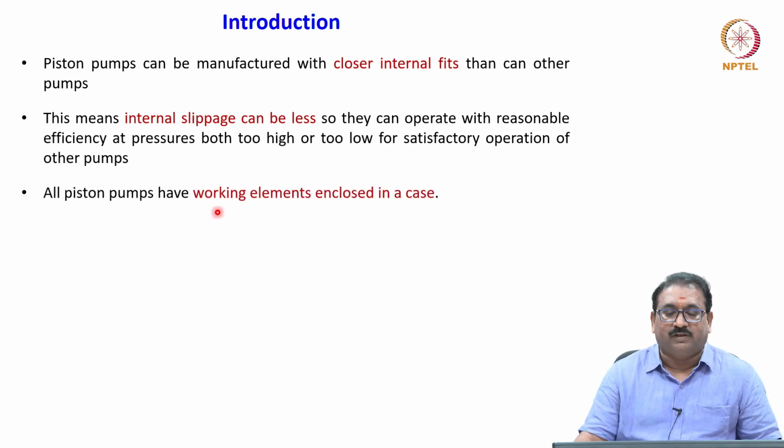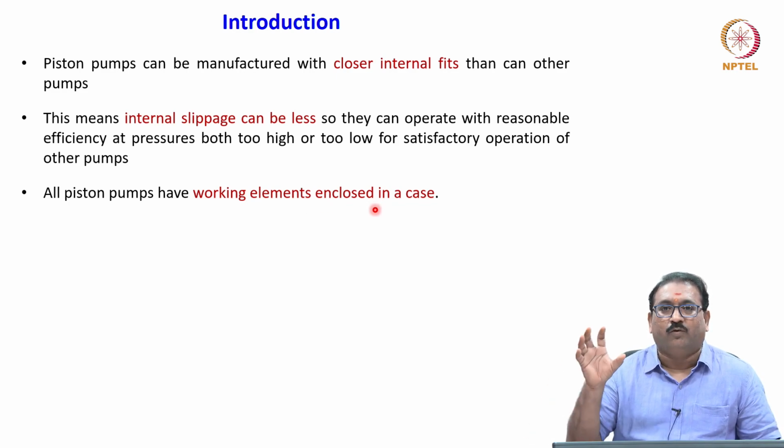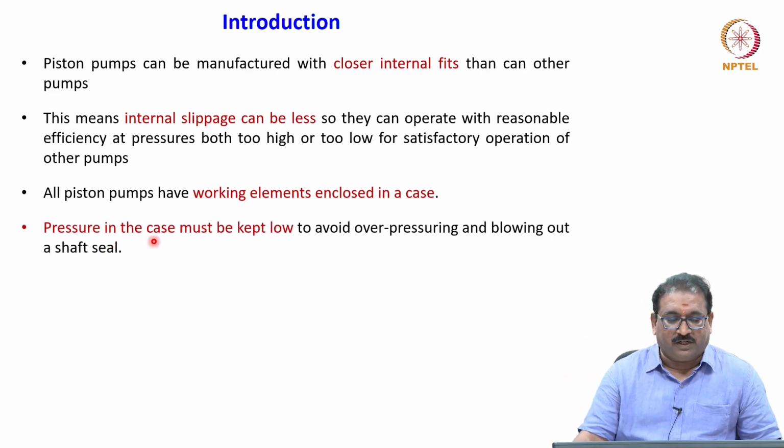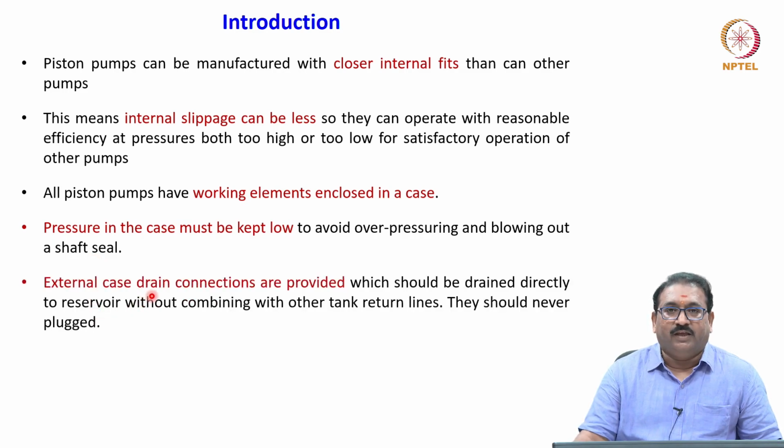All piston pumps have working elements enclosed in a case, which you can call the housing. Pressure in the case must be kept low to avoid overpressurizing and blowing out the shaft seals. External case drain connections are provided, which should be drained directly to the reservoir without combining with the other tank return lines.